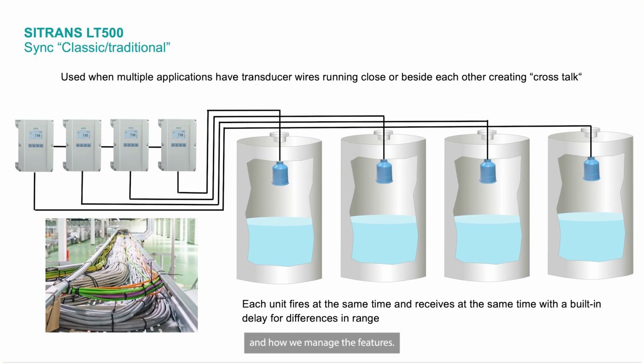And how we manage the feature is each unit all fires at the same time, or synchronously, and then we wait for each unit to receive their signal back, and we provide a delay to ensure that we manage any differences in range. If our first application is only a 3-meter range and we have another item in the sync chain which is a 15-meter range, we need to account for that difference in time of flight. So we fire all the transducers at the same time, we wait until all of the transducers can have their signal returned, and then we reset and we fire again for our next measurement.